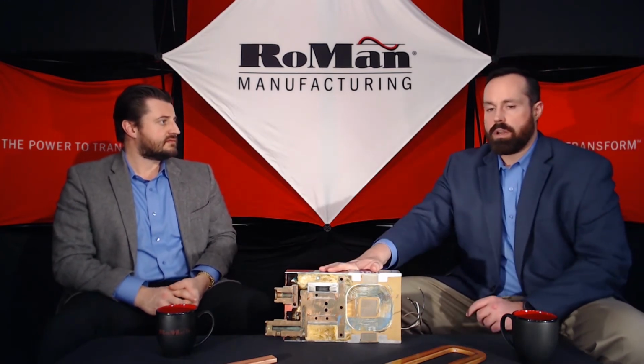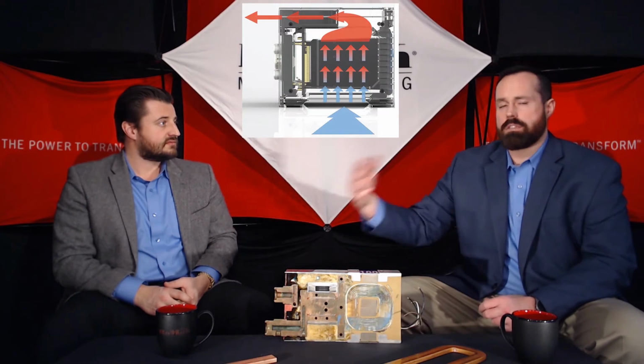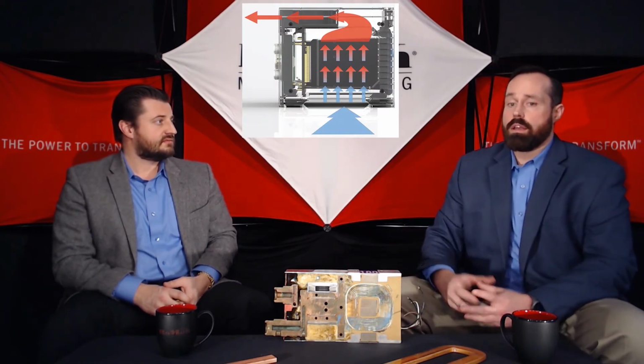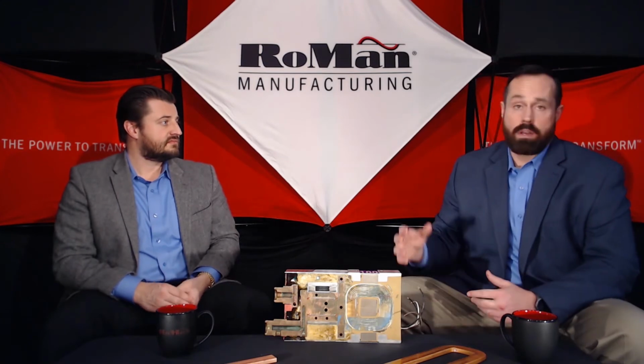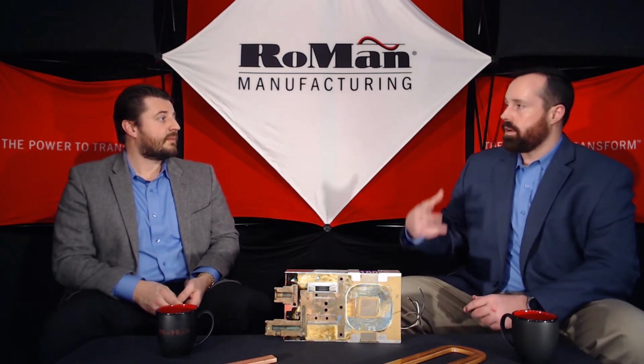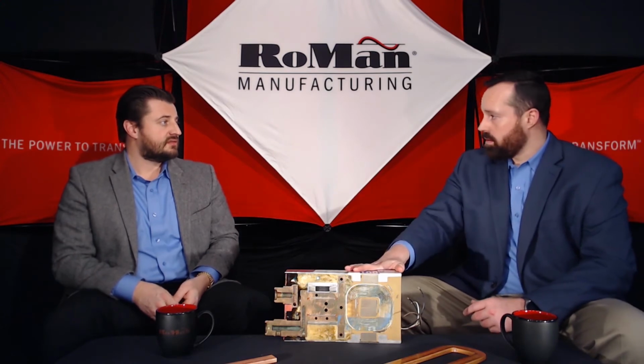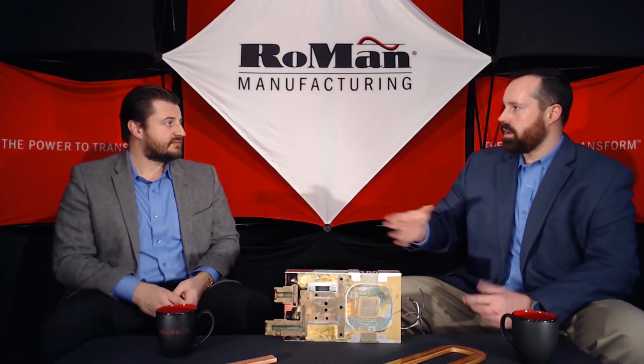So because of how a component needs to be cooled, with air, for example, that air has to be constantly circulating around that hot component. In environments where there's a lot of debris and harsh byproducts of your application, it can require more maintenance and earlier failures because that air channel is being clogged. Whereas our water channel is a closed system, so none of that debris or clogging can happen. Additionally, air-cooled devices use ambient air to cool them. And so in hot areas like furnace factories or glass applications where the ambient heat is a lot hotter, there has to be special considerations. Sure. With our water-cooled transformers, we can pipe water in from anywhere and generally stay at a reasonable temperature.